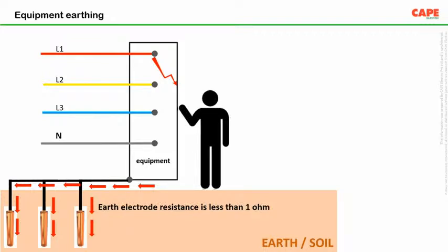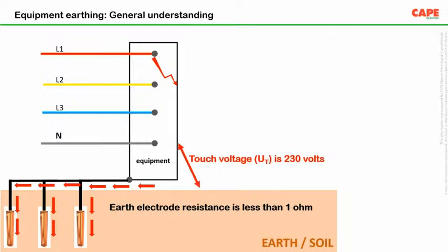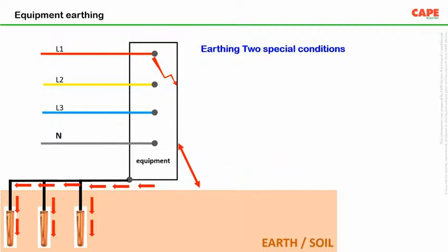This is wrong. Actually, here the earthing has nothing to do with the safety. Now, the problem is the touch voltage. Between the body, the exposed conductive part of that particular equipment, and the place where you are standing, there is a touch voltage existing. As a result, you will get a shock. The earthing is not going to help you.